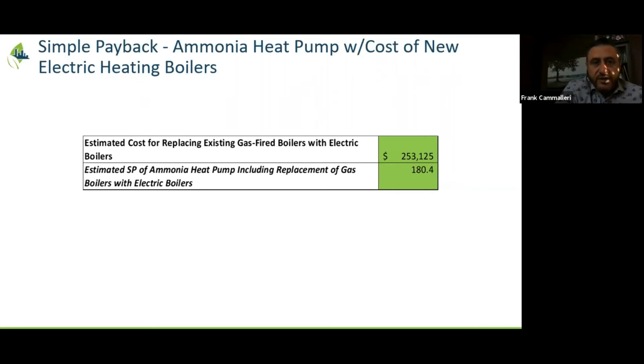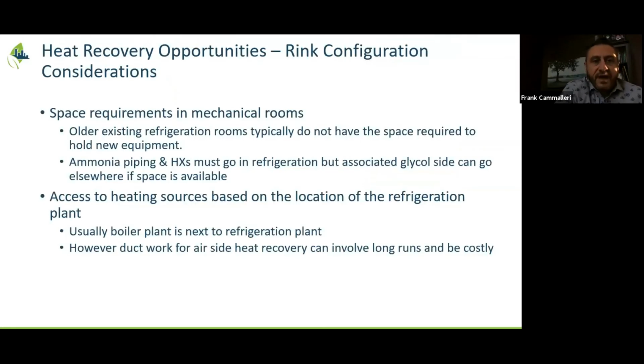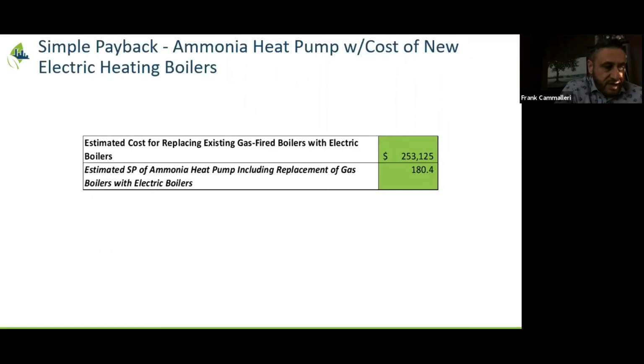A lot of information there, but the main point is that in this case, a trigger event happened: boiler replacement was required because equipment was at the end of life. What do you need to do? The preliminary analysis shows that right now you're better off still replacing it with gas-fired boilers, usually higher efficiency ones. Okay, if we can go to the next slide.